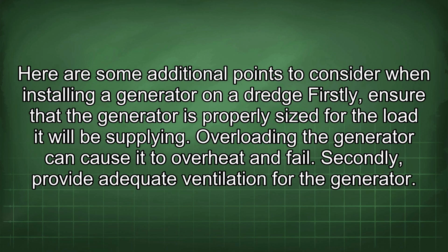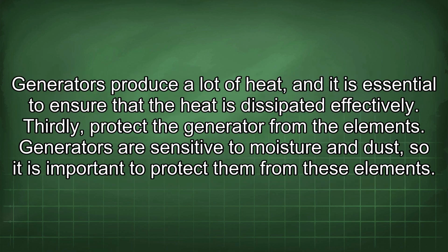Here are some additional points to consider when installing a generator on a dredge. Firstly, ensure that the generator is properly sized for the load it will be supplying. Overloading the generator can cause it to overheat and fail. Secondly, provide adequate ventilation for the generator. Generators produce a lot of heat, and it is essential to ensure that the heat is dissipated effectively.